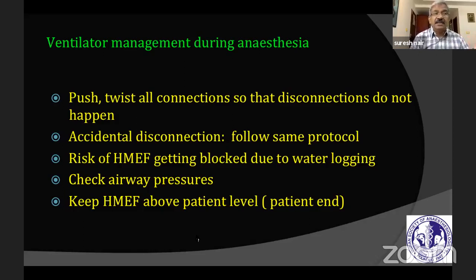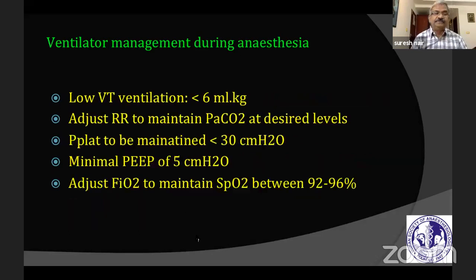Second, look at the expiratory tracings of volume or pressure - you'll find an auto-PEEP being generated, which indicates the HME filters are getting blocked. In that case, you have to change the technique. One technique that can help prevent this to some extent is to keep the filter near the patient end above the patient's head level, which will prevent too much water accumulating in that filter.